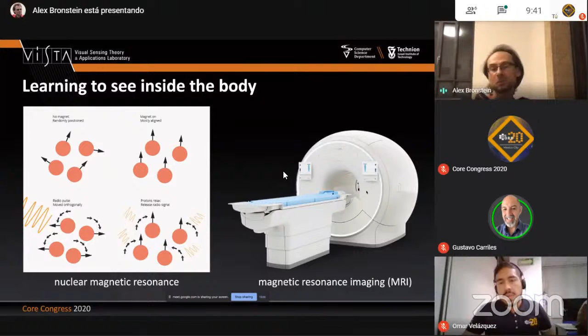And then we do Fourier analysis, of course. So basically, the MRI image is obtained directly in the Fourier domain. And by tuning the strength of the gradient coils, we can traverse the Fourier domain, either in two-dimensional space or in three-dimensional space. This is how an MRI image is acquired. Essentially, the image is scanned over a trajectory. So basically, the MRI machine is configured with a scan trajectory, and then there is an image reconstruction pipeline that takes that data, does some processing, does the inverse Fourier transform, and we get this nicely looking MRI image of the brain in this case.